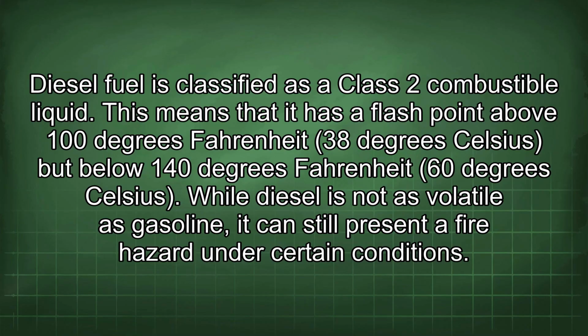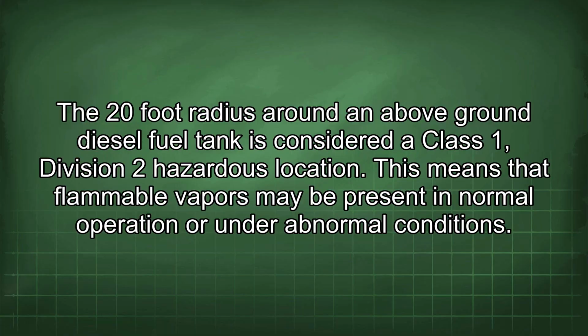Diesel fuel is classified as a Class 2 combustible liquid. This means that it has a flash point above 100 degrees Fahrenheit (38 degrees Celsius) but below 140 degrees Fahrenheit (60 degrees Celsius). While diesel is not as volatile as gasoline, it can still present a fire hazard under certain conditions. The 20-foot radius around an above-ground diesel fuel tank is considered a Class 1, Division 2 hazardous location.